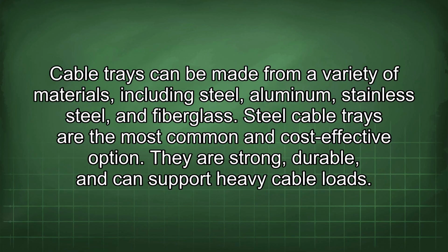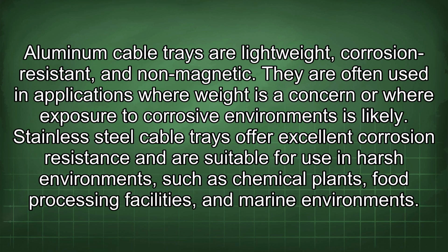Cable trays can be made from a variety of materials, including steel, aluminum, stainless steel, and fiberglass. Steel cable trays are the most common and cost-effective option. They are strong, durable, and can support heavy cable loads. Aluminum cable trays are lightweight, corrosion-resistant, and non-magnetic. They are often used in applications where weight is a concern or where exposure to corrosive environments is likely.